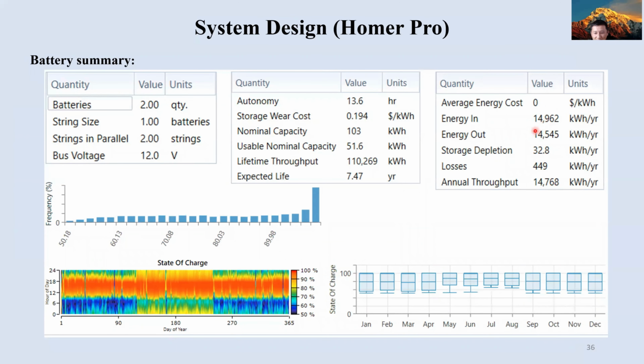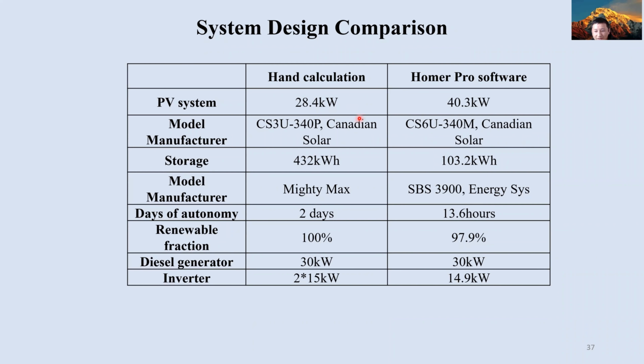This is the screenshot of the batteries summary from the Homer Pro, and it shows that the battery is mostly used in the summer months, January, February, March, and then November, and drops down to 50% of the state of charge sometimes. And the optimized battery system from the Homer Pro has 13.6 hours of autonomy, and the expected life is 7.47 years.